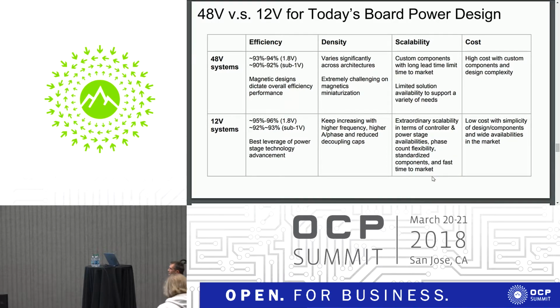This is on the motherboard only. If you just look at the motherboard, you have a higher step-down ratio for 48 volt to 1 volt compared to 12 volt, so the efficiency is lower there. But the majority of the savings is at the rack level, and a lot of other presentations already address the benefit of this saving on the front end, AC to DC, and then the bus bar in the rack. That's the majority of the benefit, and where it's coming from.